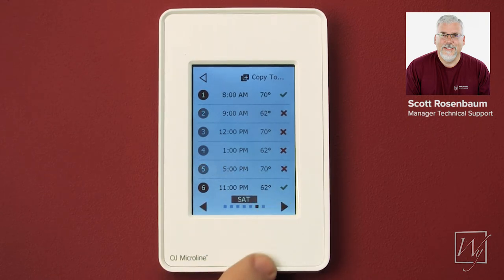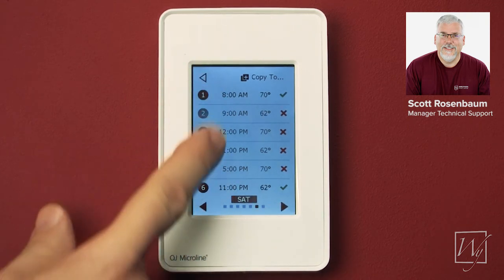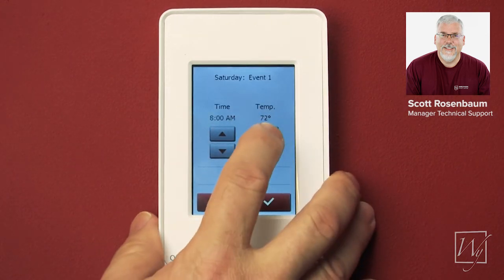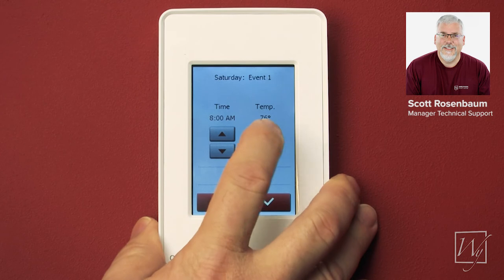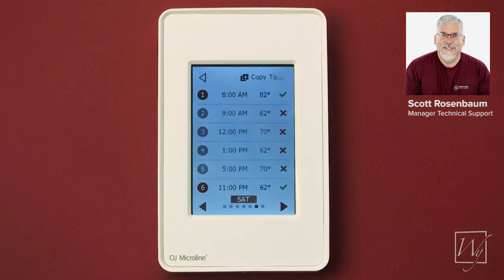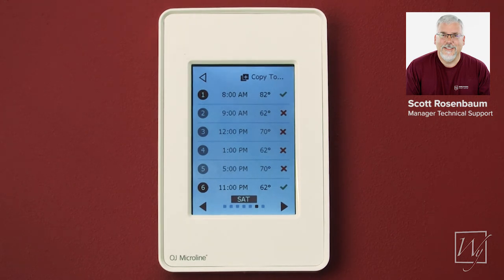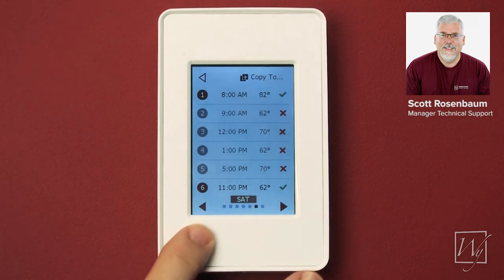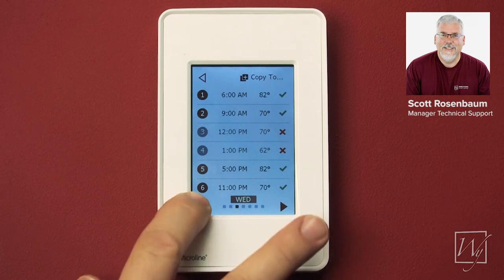If you want to change Saturday, go in and you can leave it on all day. If you want to change the temperature from 70, adjust the floor temperature up to 82, since that's what we're used to — once again you can set this to whatever you want. If you have carpet or laminate, please see the instructions for the limitations for those products; they'll tell you what the maximum temperature can be, and we suggest setting it to that. That's how you do your settings on our new touchscreen units.